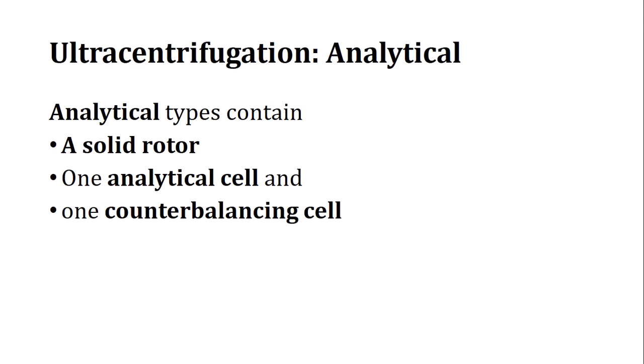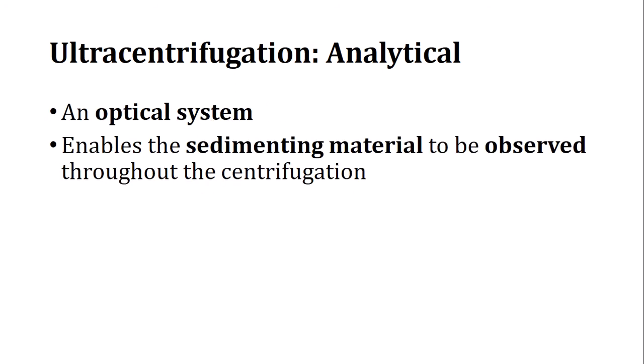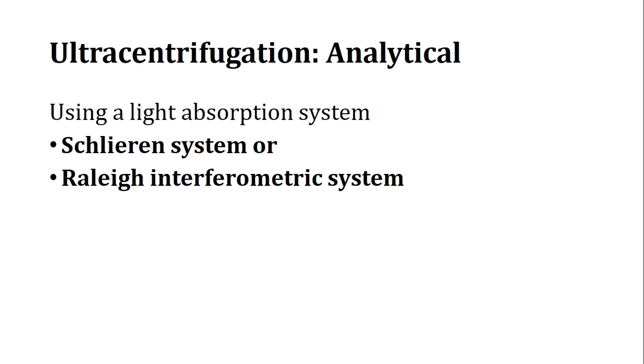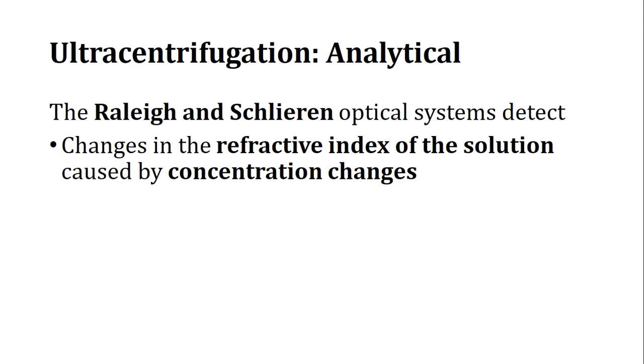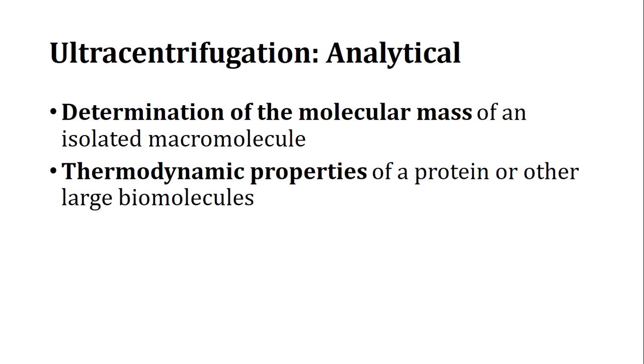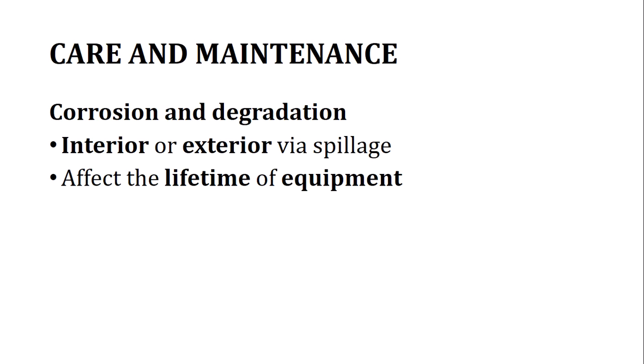The analytical ultracentrifuge contains a solid rotor, an analytical cell, and a counterbalancing cell. It has an optical system that enables sedimenting material to be observed throughout centrifugation. Using a light absorption system — called the Schlieren system or Rayleigh system — both optical systems can detect changes in the refractive index of the solution caused by concentration changes. Applications include determination of molecular mass of isolated macromolecules and thermodynamic properties of proteins and large biomolecules.